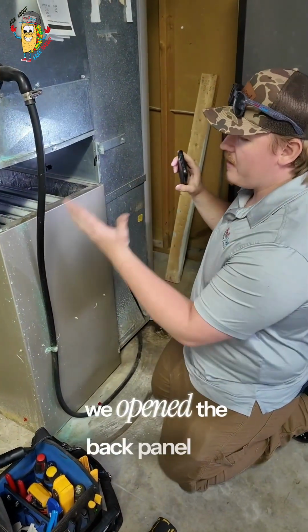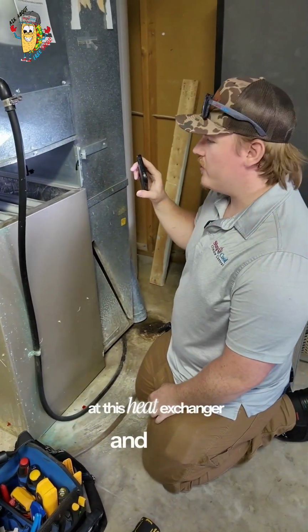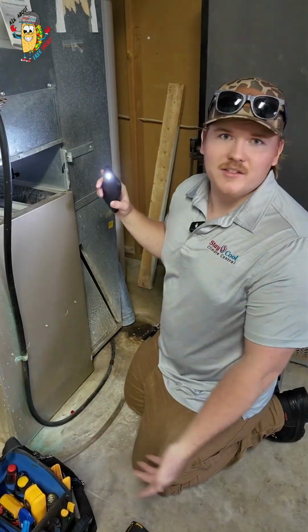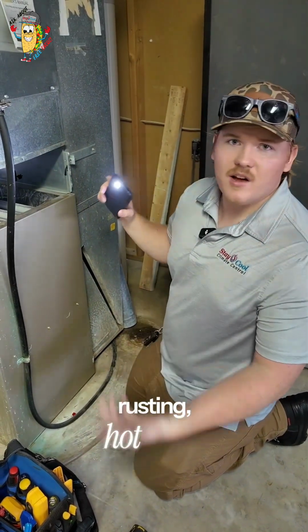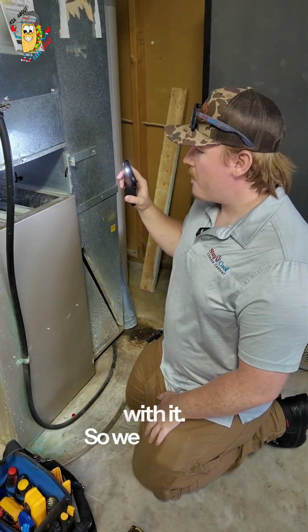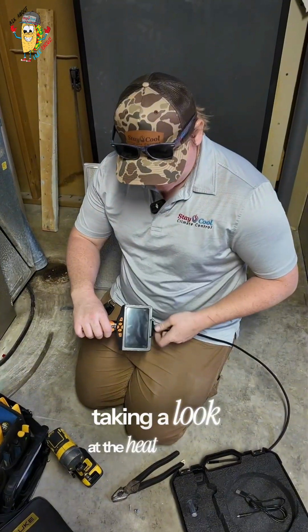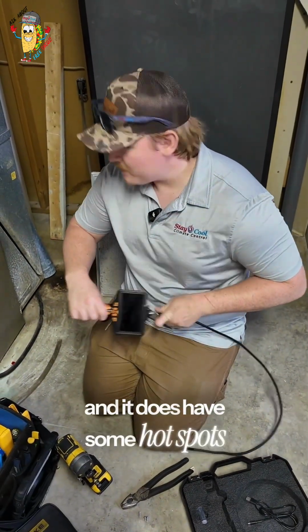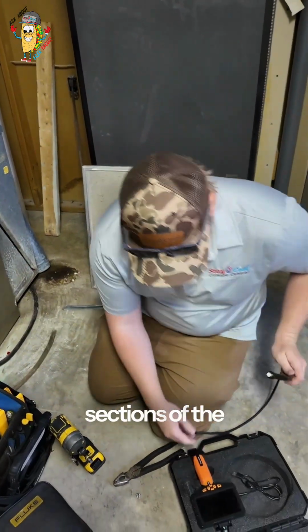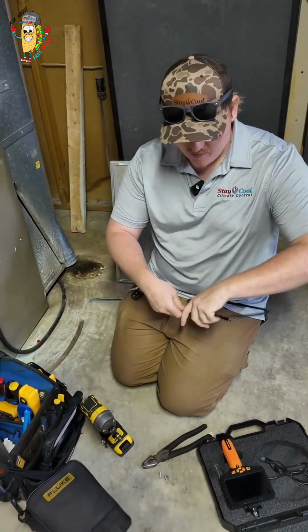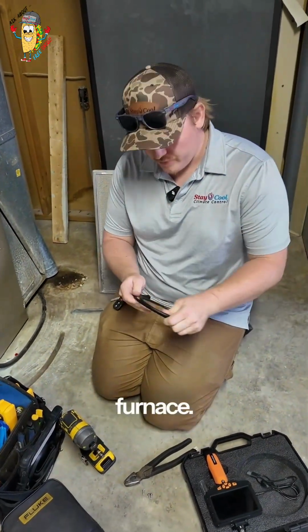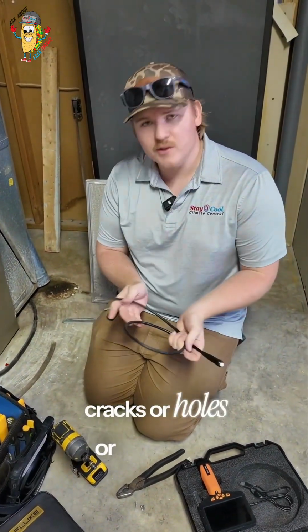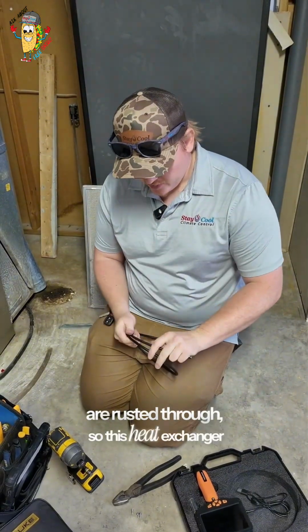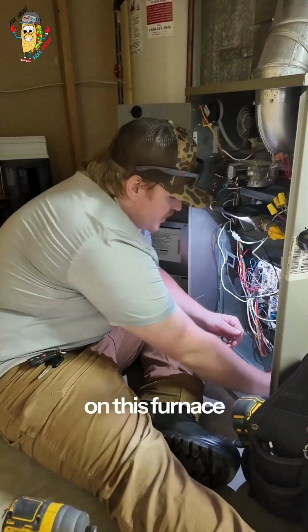So, we opened the back panel up here and we're gonna take a look at this heat exchanger and see if it's got any cracks, any rusting, hot spots, see if there's any problems with it. So we got done taking a look at the heat exchanger, and it does have some hot spots on it, just sections of the metal where it's heated up a lot over time, which is perfectly normal for a 14-year-old furnace. Didn't find any cracks or holes or spots that are rusted through, so this heat exchanger looks safe. We got everything on this furnace checked out.